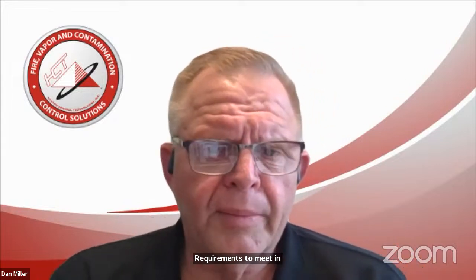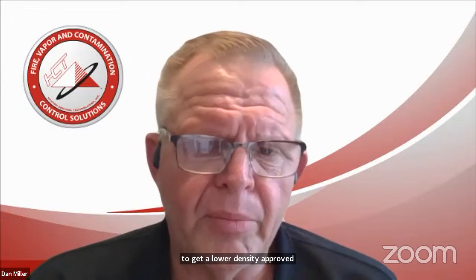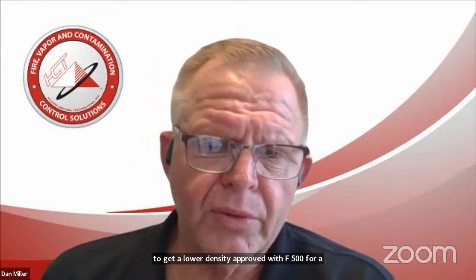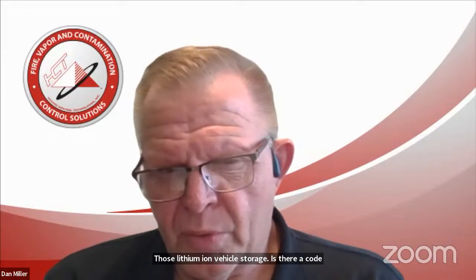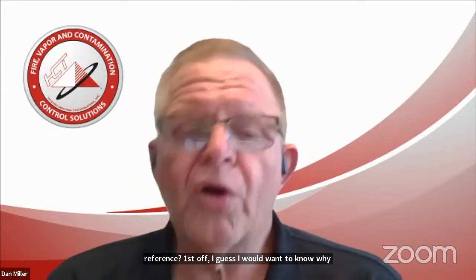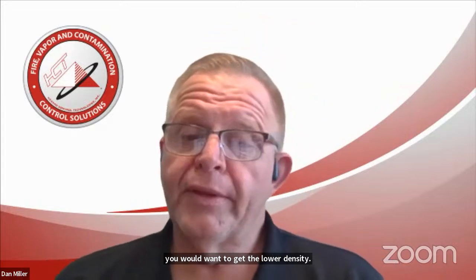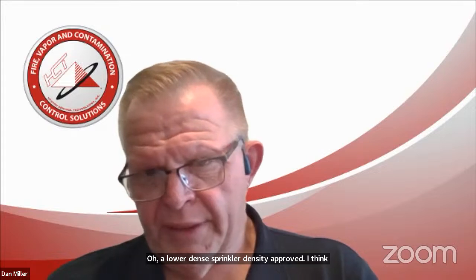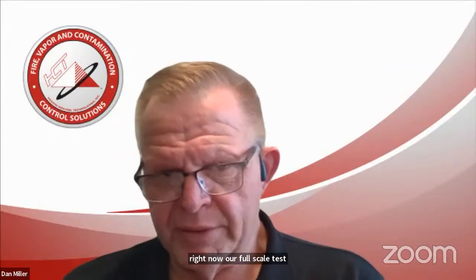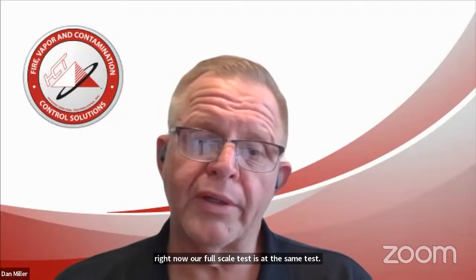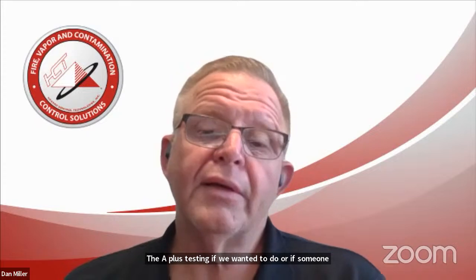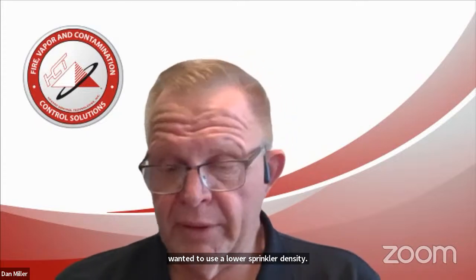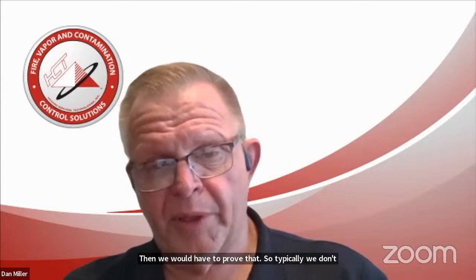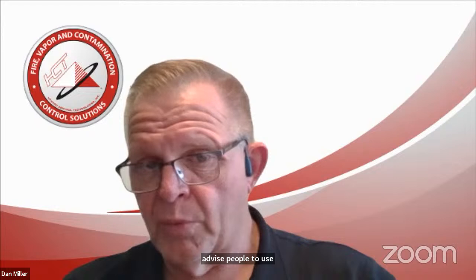Doug Delabro asks, would you be able to get a lower density approved with F500 for a project that is lithium ion vehicle storage? Is there a code reference? First off, I'd want to know why you would want a lower sprinkler density approved. Right now our full scale test is at the same A+ testing. If someone wanted to use a lower sprinkler density, we would have to prove that. So typically we don't advise people to use a lower sprinkler density than plain water.